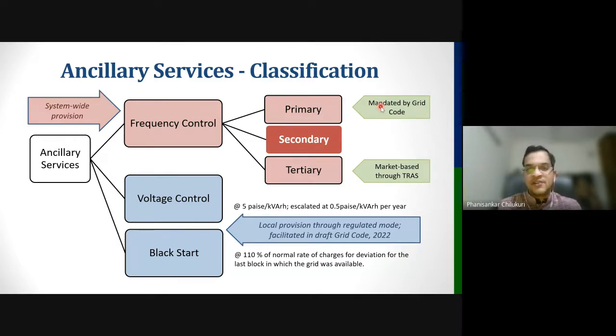In primary frequency control, the governors at the power plants locally sense the frequency and adjust in such a way that generation increases or decreases based on local frequency sensing. So based on a predefined droop characteristic, the generator might produce more or less power. If there is low frequency, the generator would produce a little more power. If there is high frequency, the generator will produce less power.